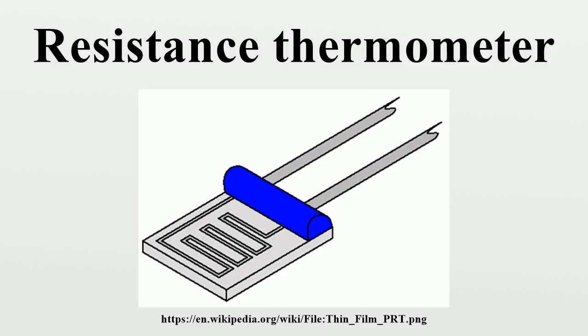The sensing wire is connected to a larger wire, usually referred to as the element lead or wire. This wire is selected to be compatible with the sensing wire so that the combination does not generate an EMF that would distort the thermal measurement. These elements work with temperatures to 660 degrees Celsius.